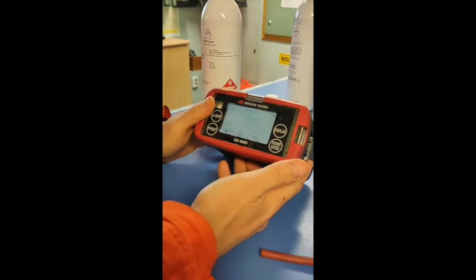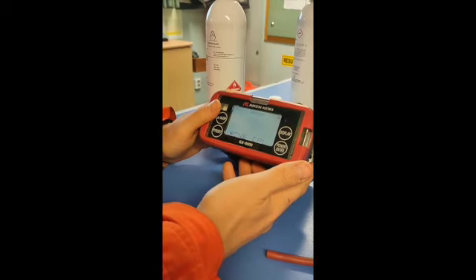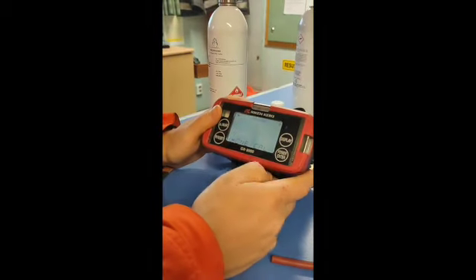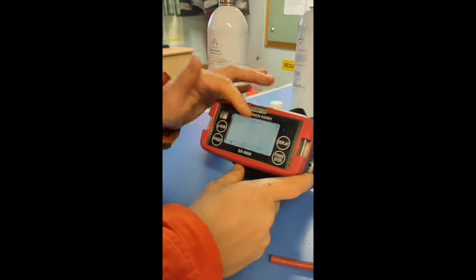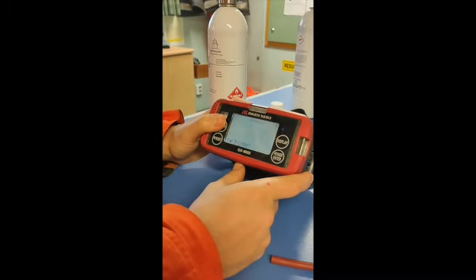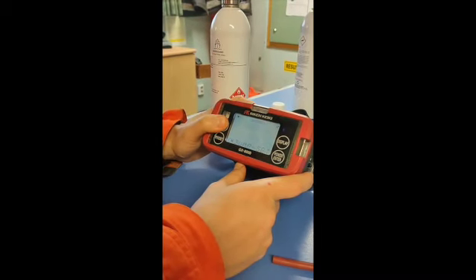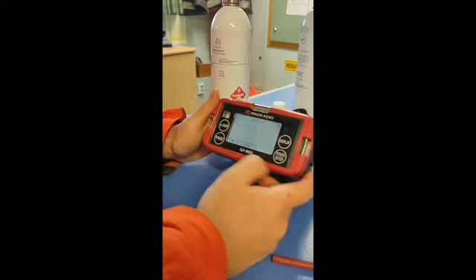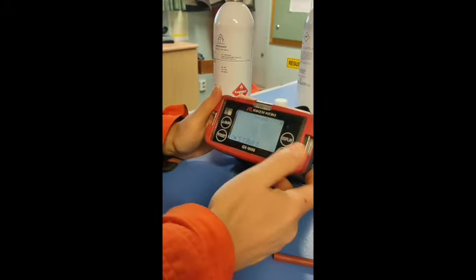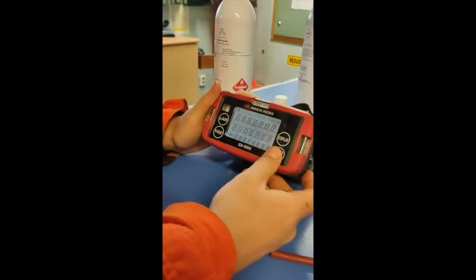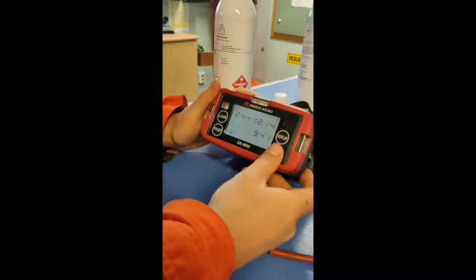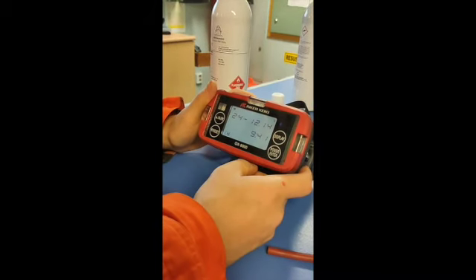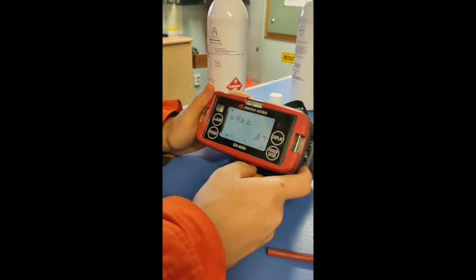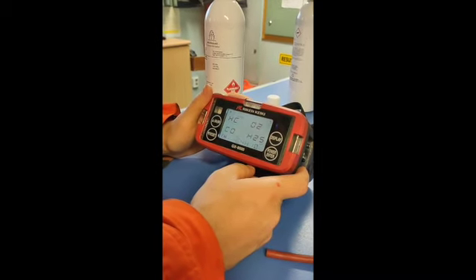And this is the full calibration explanation in the maintenance mode. You cannot go in other mode. This is the maintenance mode. It's only one. To go out from this menu, just press start or long press enter to switch off the portable gas detector. That's all. Thank you very much.